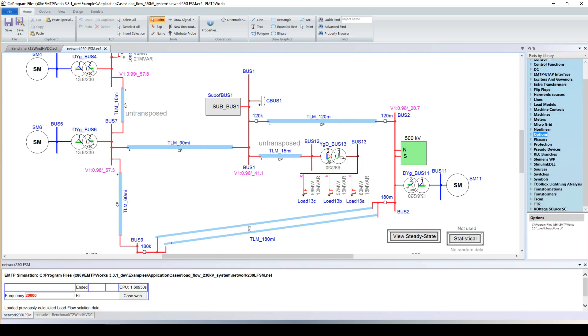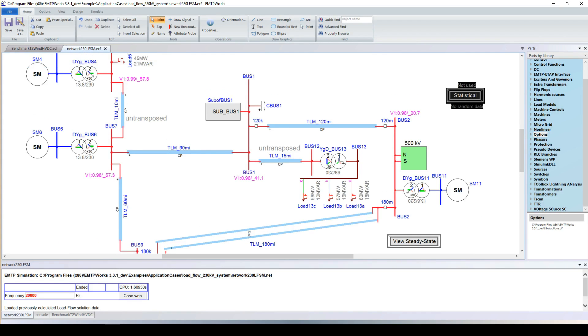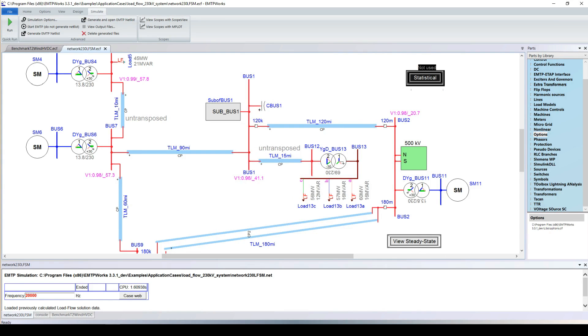To perform the statistical switching study, we simply parameterize the statistical option device. We go back to time domain simulation, and EMTP will automatically run hundreds of simulations, changing the switching time between each one. To go faster, since we're only interested in the first cycle after the capacitor bank switch, we reduce the simulation time. We also decrease the time step to be more precise. We enable the statistical option and choose the number of simulations — for this demonstration, 50, though in practice up to 500 for precision.